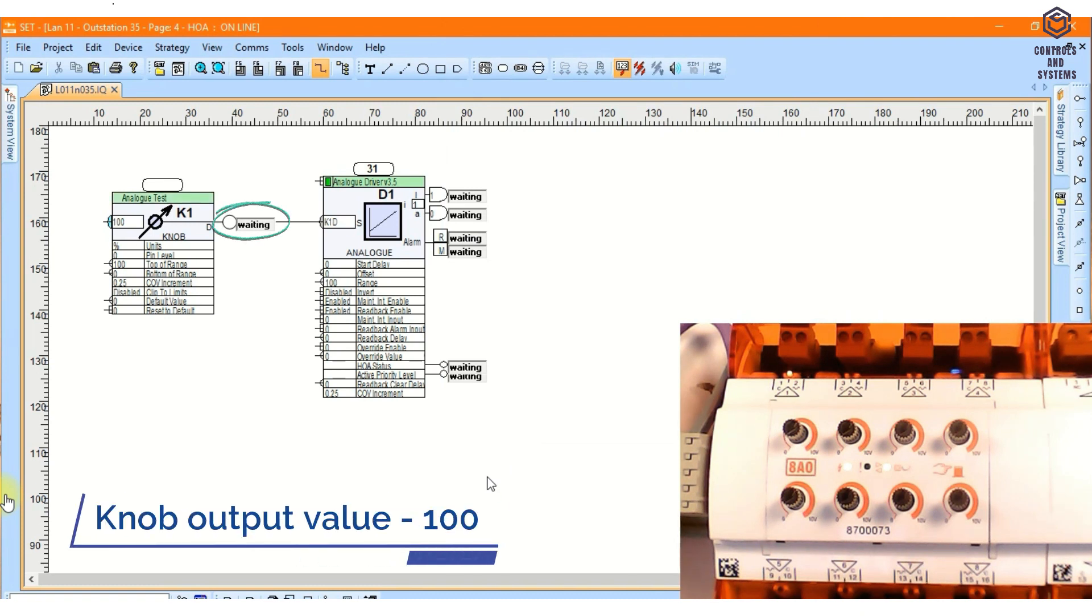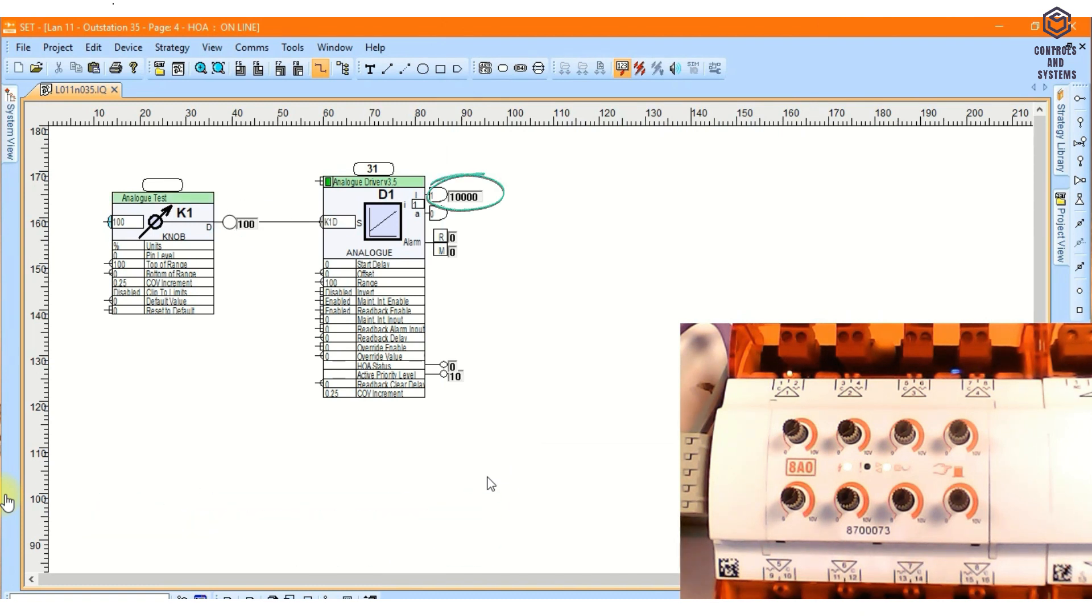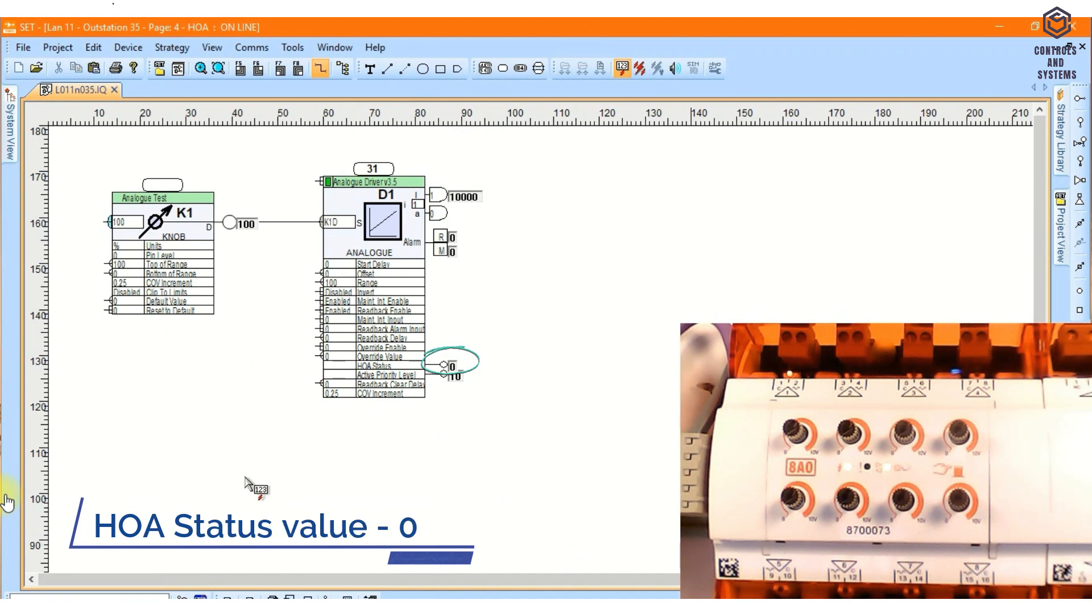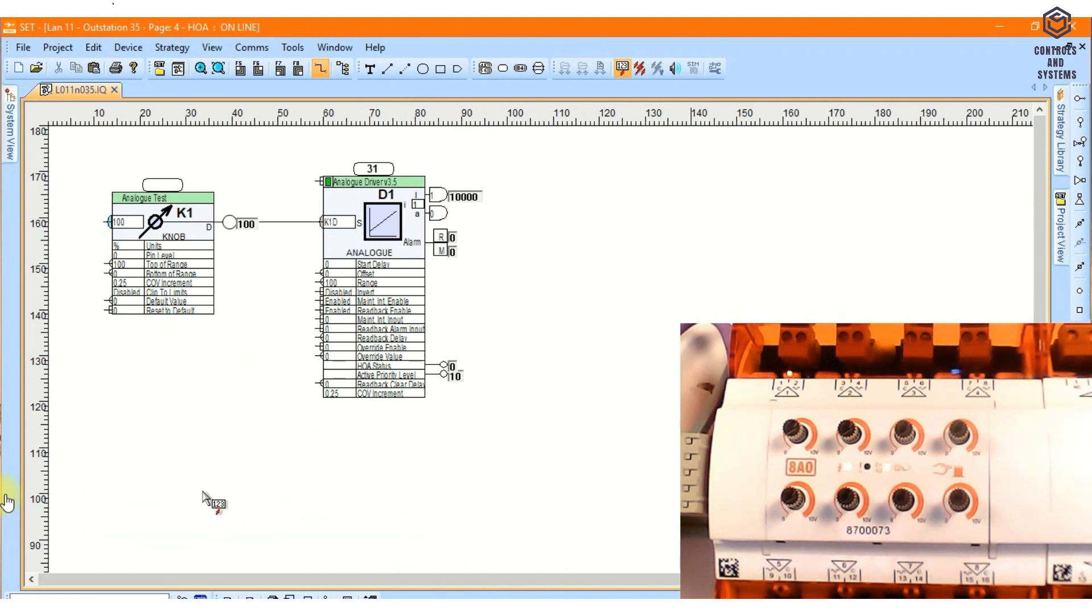Knob output value is 100, analog driver output value is 10,000, which means input 10 volts on our output, and HOA status is 0. The driver is in auto, so the HOA status is shown at 0.